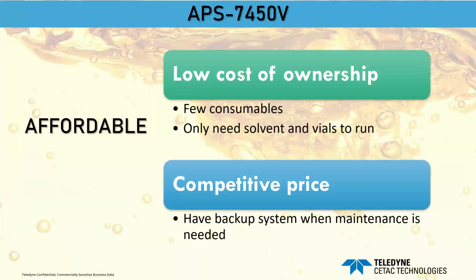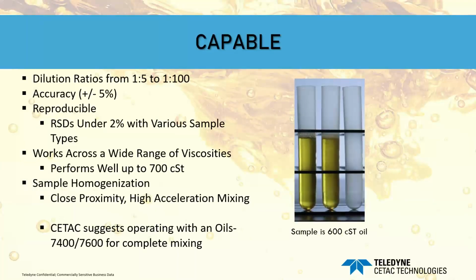All right, and it is capable. Sticking with the horse theme I started earlier and seem to be developing here, the APS 7450V is not a one-trick pony. It's not just fast, it is capable as well. It can handle dilutions from 1 to 5 up to 1 to 100, and it does this while maintaining accuracy of plus or minus 5% with RSDs under 2%. It works with a wide range of viscosities and performs well up to 700 centistoke.